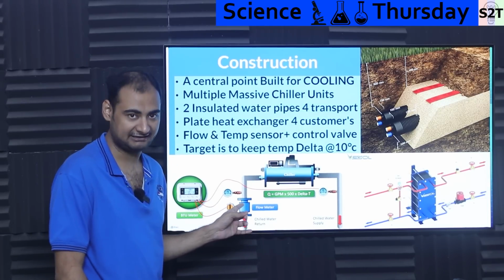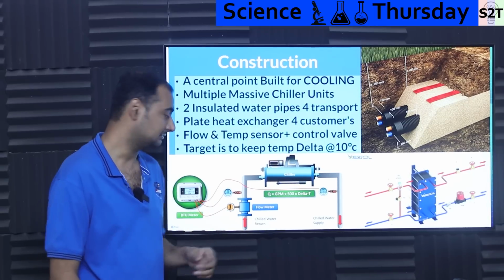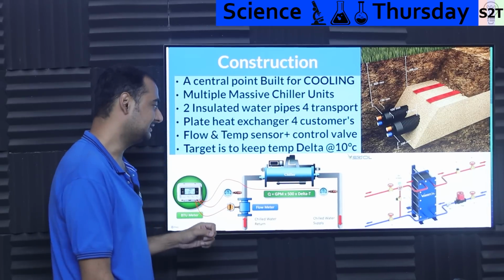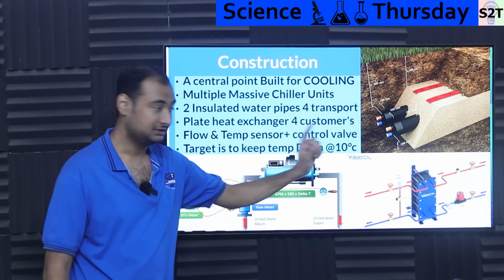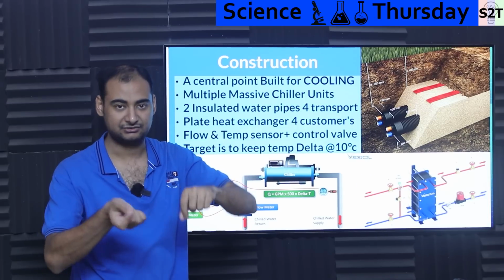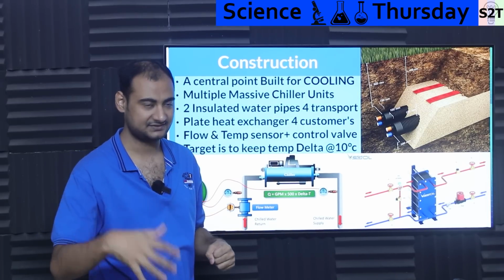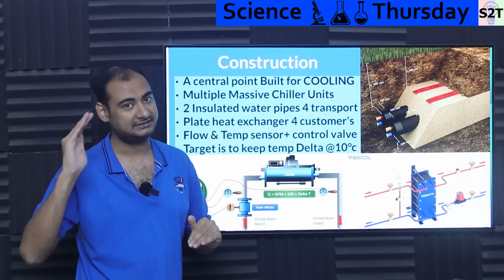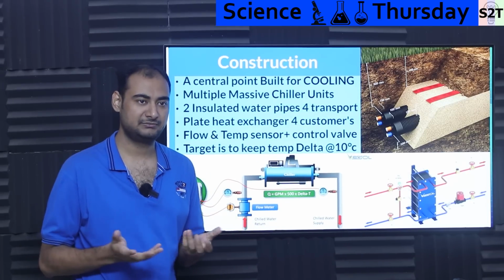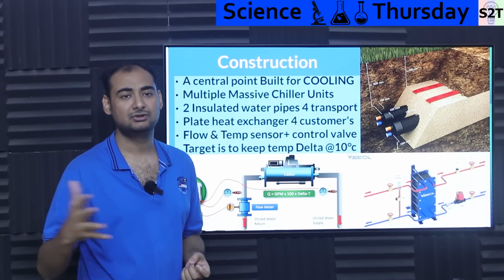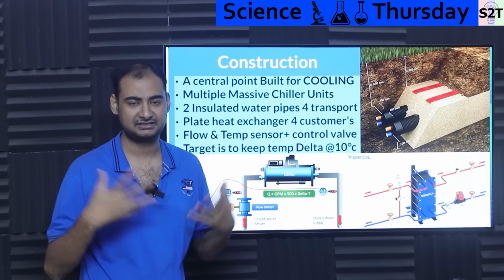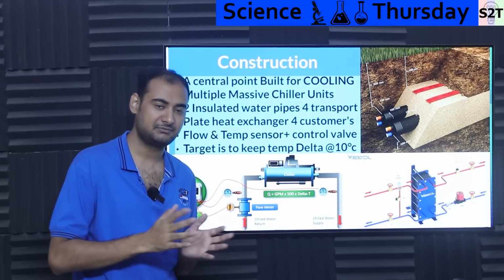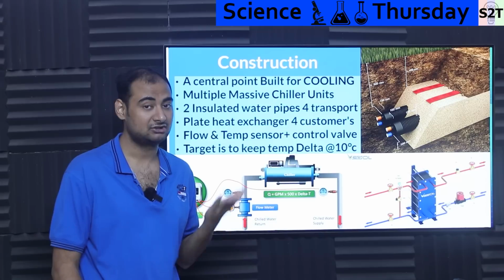First, you need a control valve that actually allows you to control. Second, you need two thermal sensors. So basically you measure how much is going in. So the going-in part, basically what is coming to you, would always be at 4 or 5 degrees Celsius. And the out part should be at 10 degrees up. Now, how does the system maintain it? The system controls the flow. For example, you are dumping very little heat into the system. Let's say there is no load in your building. You are dumping very little heat. But again, the temperature will not go to 10 degrees Celsius.